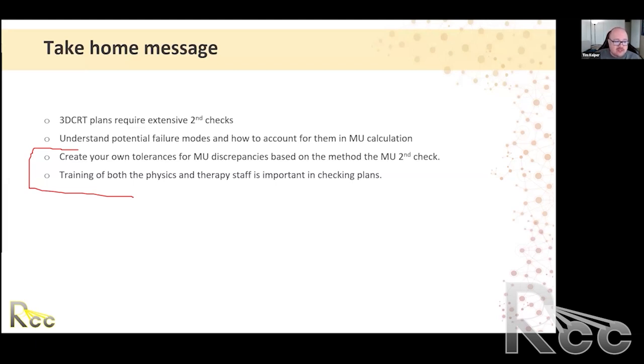And then I have one more question that came a lot earlier, and it basically boils down to, do all centers need to use the same calibration conditions and 1 centigray per MU calibration? And if not, how does that go into the equations, or how do we use these different scenarios for our machine calibration? Also a good question. So centers do not need to have the same reference geometry. I have worked in centers that calibrate their LINAC with SSD, so 100 cm SSD, at Dmax, with a 10 by 10 field size, of course, always open beam. I've also worked in centers, or actually went and trained others in centers, where their LINAC is calibrated SAD. So the LINAC is SSD 90, depth of 10 cm. So that's 100 cm to isocenter, right? And then they used TPR instead of PDD.